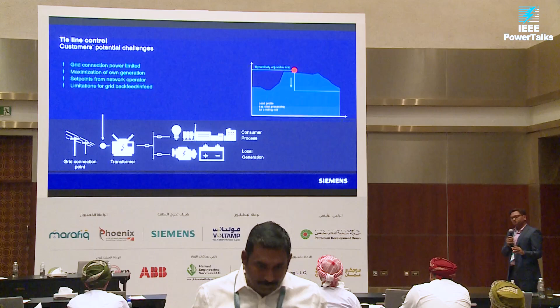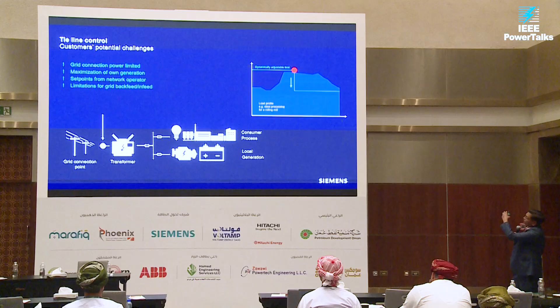So in this case, suppose without microgrid control, the assets are there, you can see sometimes up, down, power supply consumption varies. But if you use tie line control with our microgrid controller, you can see from where we highlighted this line, after that it's a very steady line. The microgrid controller, based on your set point, puts the set point on the point of common coupling or tie line, and you can say this is the required power you can import, or this is the required power you can export to grid.